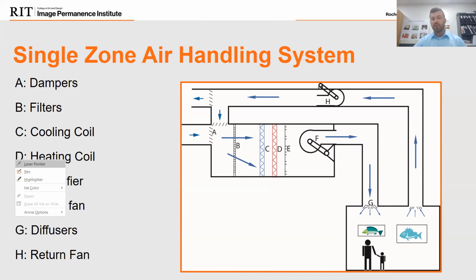The question that was asked earlier, the design of this, there can be a number of different designs just to this unit alone. So what I gave here is a basic example. In one scenario, these coils can be flipped where it only heats or only cools. And in that scenario, we will not do any dew point change. The air will just be, as we discussed earlier, sensibly heated, sensibly cooled. There can be what they call preheating or pre-cooling coils, where there's a cooling coil that's going to precondition the air before it gets to the coil. So depending on the type of system you have, it could be different.